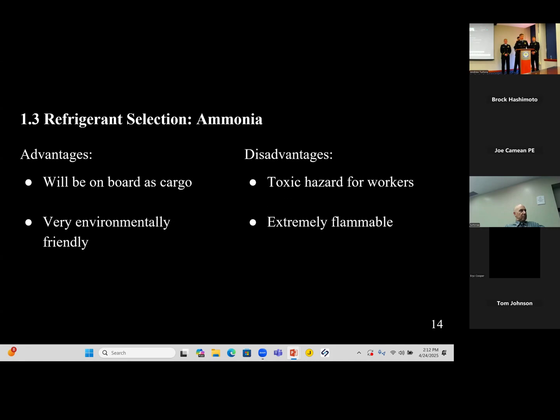So the next thing we're going to look at is ammonia. Now, there are a lot of old systems that use ammonia as a refrigerant. And if you don't know, it's actually coming back into fashion because ammonia has a low global warming potential. Now, while that's good, and also with the consideration that we're going to have ammonia on board as cargo, so we're already going to be prepared for some of that, the disadvantage to ammonia is it has a toxicity hazard for workers, as well as a high flammability under pressure. There's been multiple reports from both OSHA and the EPA about the hazards related to ammonia refrigerant, particularly in the marine environment. So for that reason, we decided for the safety of the crew that we were going to not use an ammonia system.